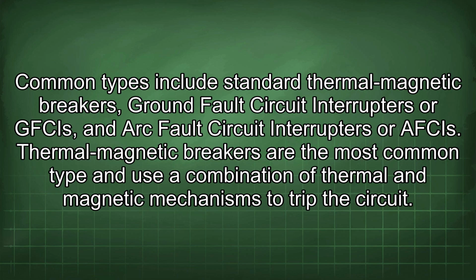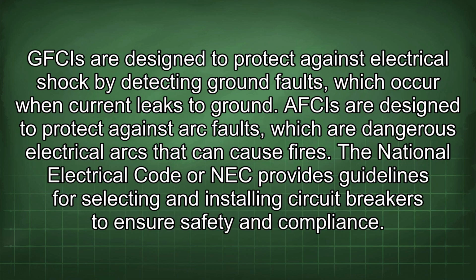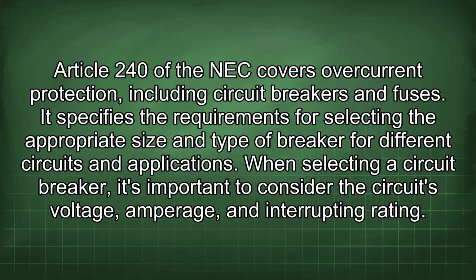Thermal magnetic breakers are the most common type and use a combination of thermal and magnetic mechanisms to trip the circuit. GFCIs are designed to protect against electrical shock by detecting ground faults, which occur when current leaks to ground. AFCIs are designed to protect against arc faults, which are dangerous electrical arcs that can cause fires. The National Electrical Code or NEC provides guidelines for selecting and installing circuit breakers to ensure safety and compliance. Article 240 of the NEC covers overcurrent protection, including circuit breakers and fuses.